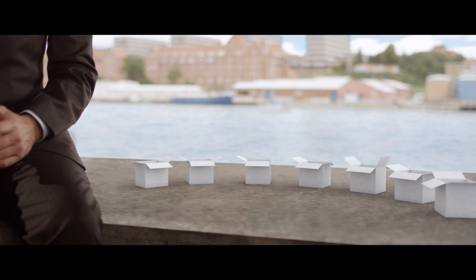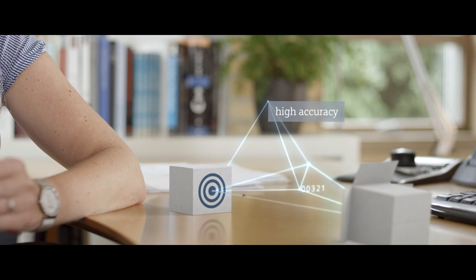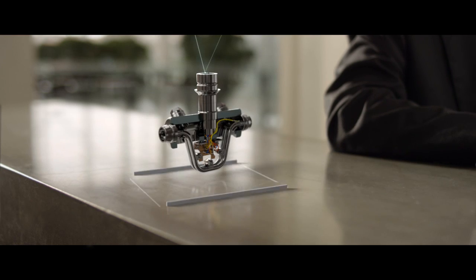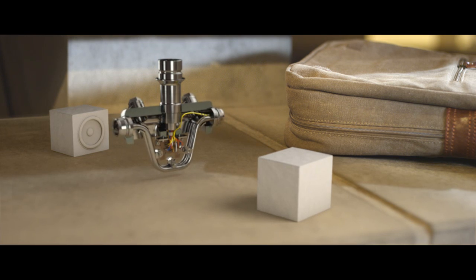You have all the great benefits inside, like very high accuracy at 0.1%. That's because of the special tube shape — the compact curve — for optimal measuring of even the smallest flows. You have high driver frequency, up to 700 Hz, which gives your flow meter excellent robustness, making installation possible in any location.